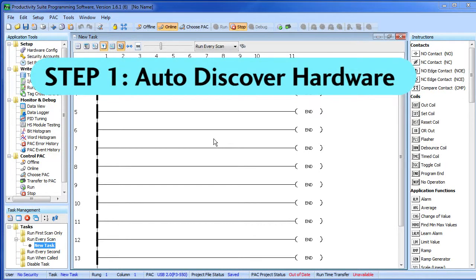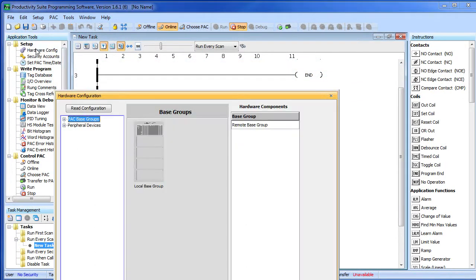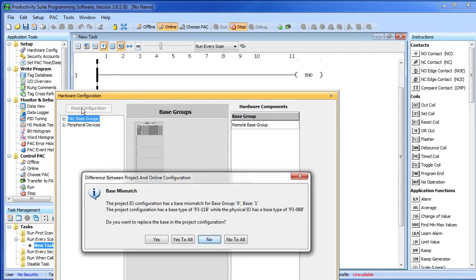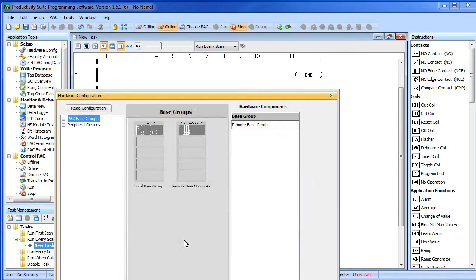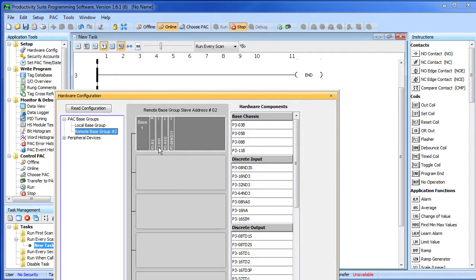Step 1 – Auto-discover the hardware. Click on the hardware configuration and then read the configuration. Remember, you have to be in stop mode to read the configuration. The software is now going to tell us all the new modules it found. We'll just say yes to all. We now have a fully populated system with a local base and a remote base with our HSI and HSO cards.